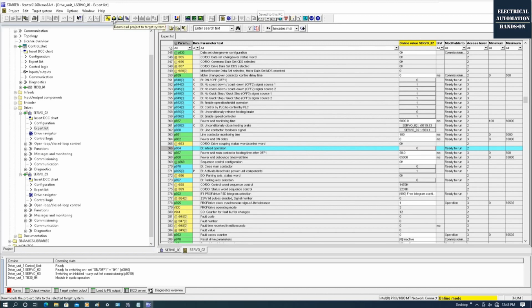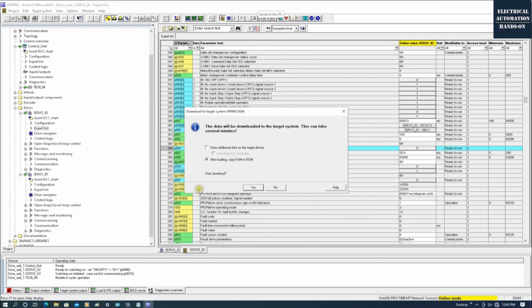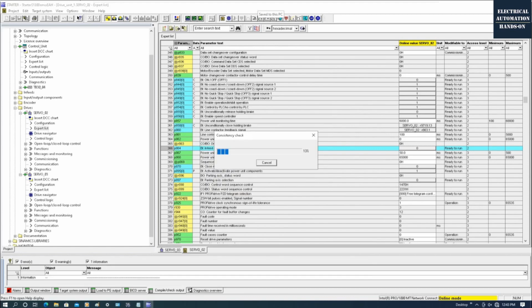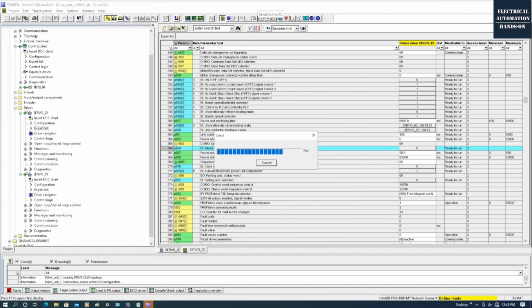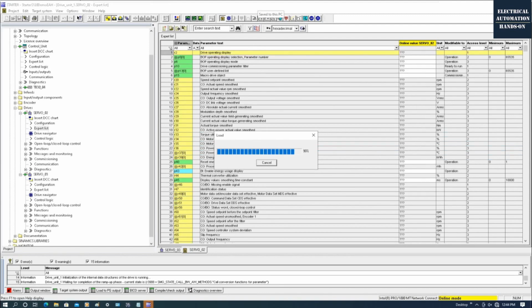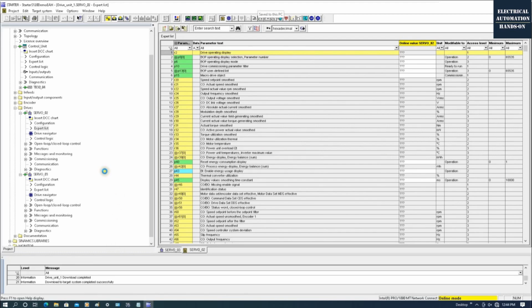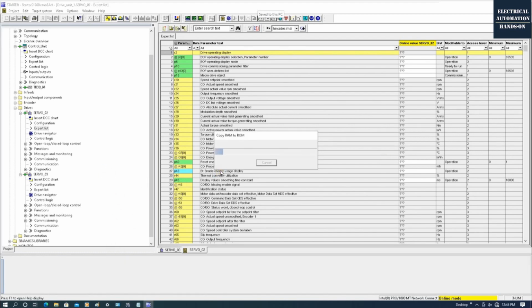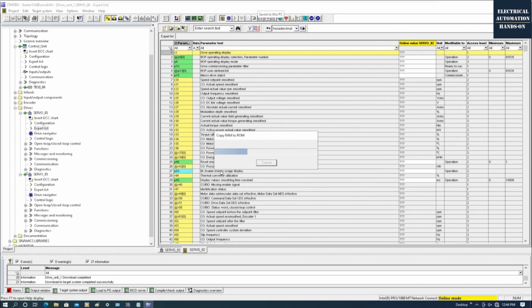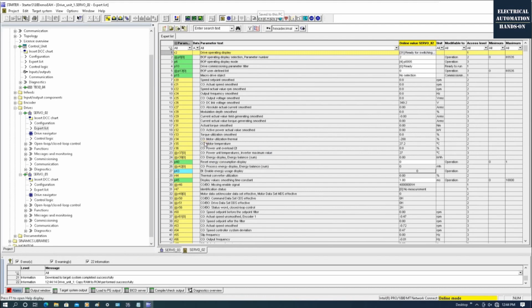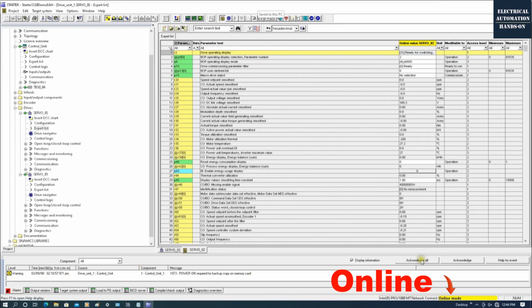Okay, we go online. Let's click this download, and I will check copy RAM to ROM, basically doing an initial setting. We copy all the settings from RAM to ROM. We still have some parameters that need to be set, but so far I will download all the hardware configuration to make sure the basic hardware can work. Okay, we finished this download, and we can see on the left side it shows green. That means my offline hardware configuration matches the real online hardware.